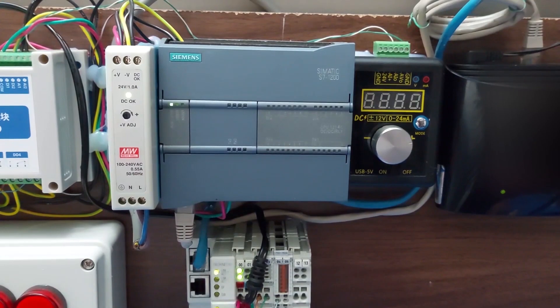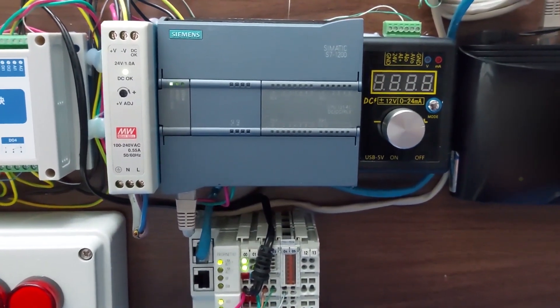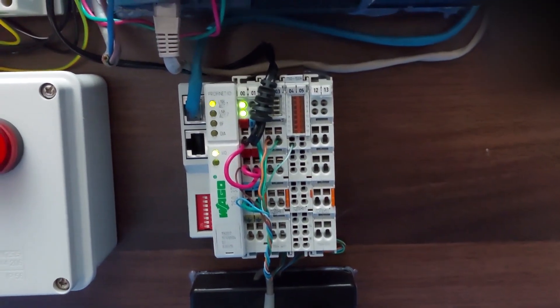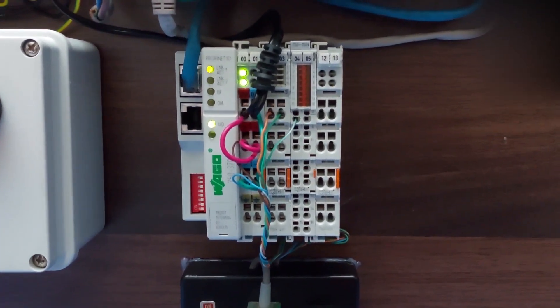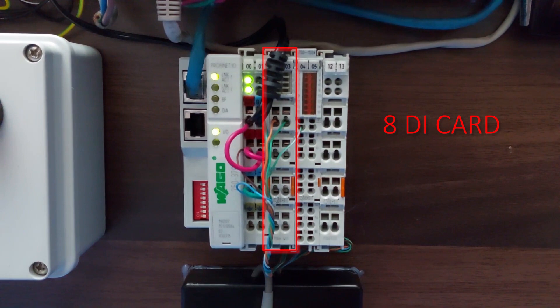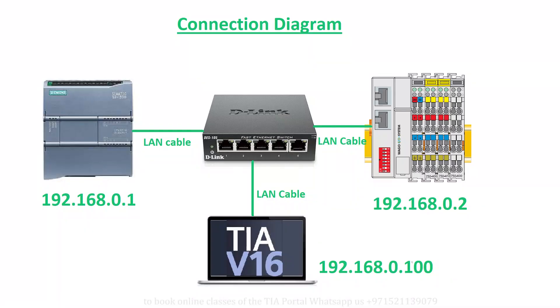As you can see, we have connected S7-1200 PLC with the Fieldbus Coupler 750-370 with Ethernet cable. We have inserted one input card with 8 digital inputs and one digital output card with 16 outputs on the WAGO Fieldbus Coupler.